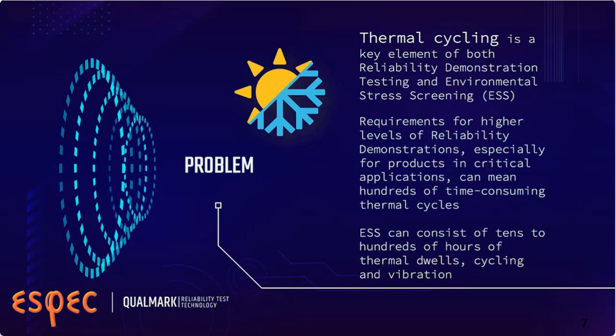If you look at, for example, requirements for solar panel testing in IEC 61215, they're talking about 10 to 200 cycles that could take up to 10 days. If you look at IPC 9592A, those are recommendations for requirements for power conversion devices.